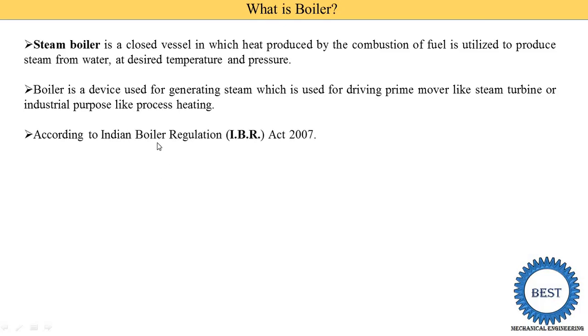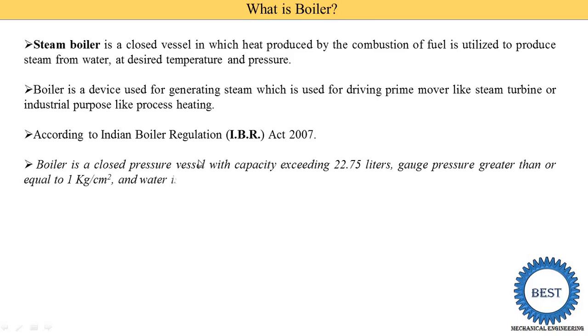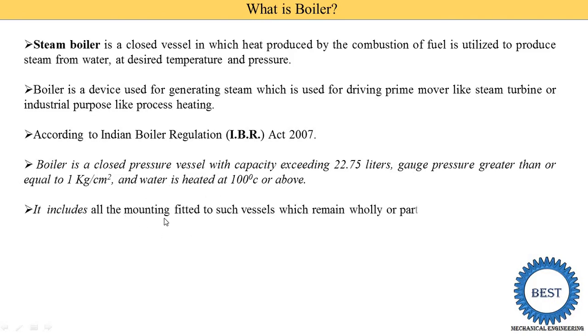According to the Indian Boiler Regulation Act 2007, a boiler is defined as a closed pressure vessel with a capacity exceeding 22.75 liters, a gauge pressure greater than or equal to 1 kg per centimeter square, and water heated at 100 degrees centigrade or above. This includes all mountings fitted to such a vessel which remain wholly or partially under pressure.